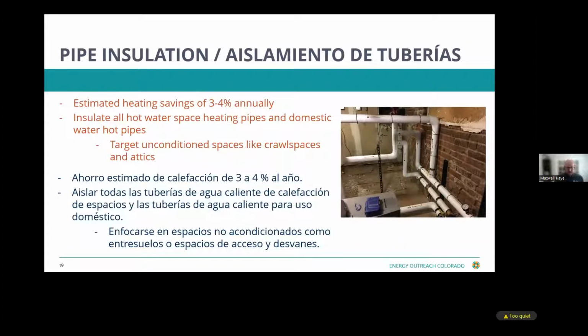But where it's having the biggest negative drawbacks are the farthest point uses from this primary system. So think about where's the shower that's the farthest away from this boiler. And by the time it gets there, if those pipes aren't insulated, you're experiencing so much heat loss over so many linear feet that your boiler plant or your hot water heater is having to work much, much harder to deliver 100-degree water to the farthest shower head in that building, or if it's a hydronic baseboard, 140-degree water to the farthest baseboard in that building.